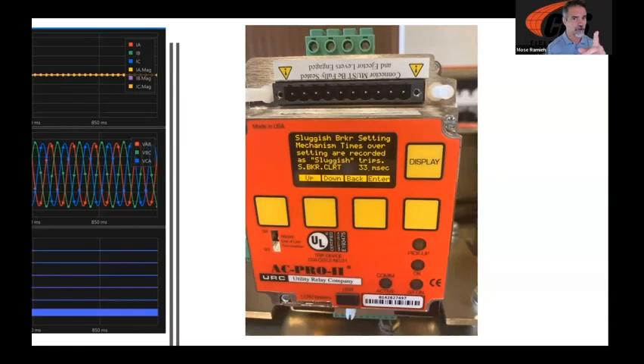And once again, it is important. I'll point out to everybody that when you modernize your breaker to an AC Pro 2 and you set up this sluggish breaker trip, when you're doing your trip testing on the high current test set, which you should do, of course, right? Anytime you've modernized a breaker, document what the average is of your trip times, right? How long does that breaker take to trip? Because it could be that it takes a little bit more than 33 milliseconds, which is the default setting. And so you might need to adjust that up a little bit to make sure that that breaker is going to be monitored properly.